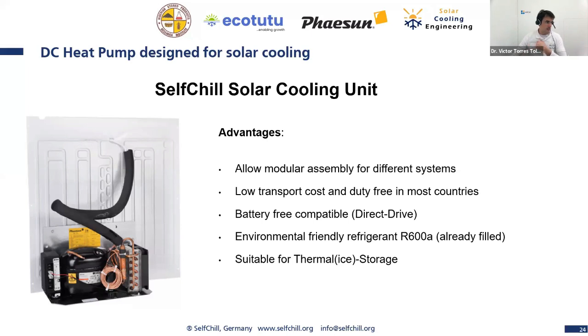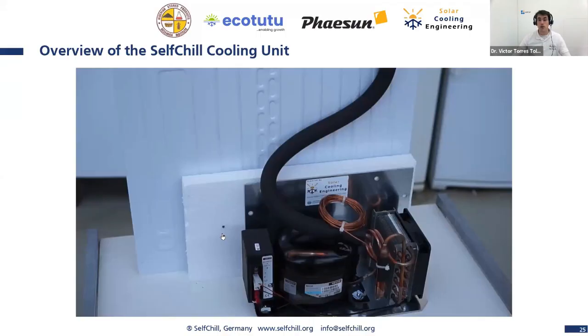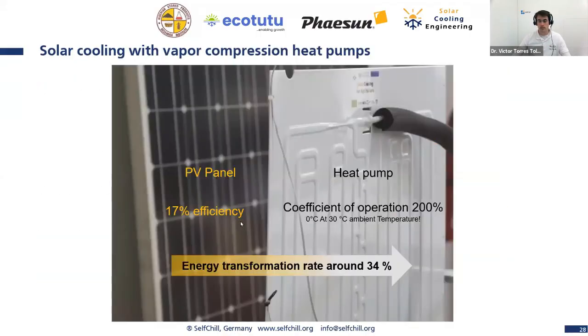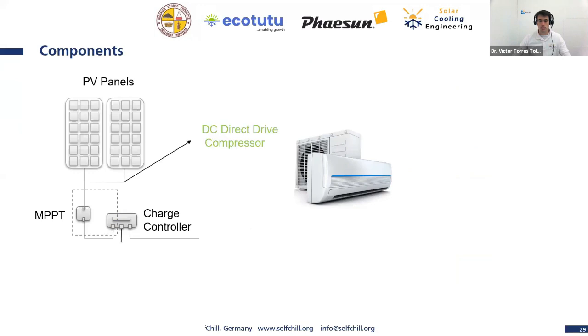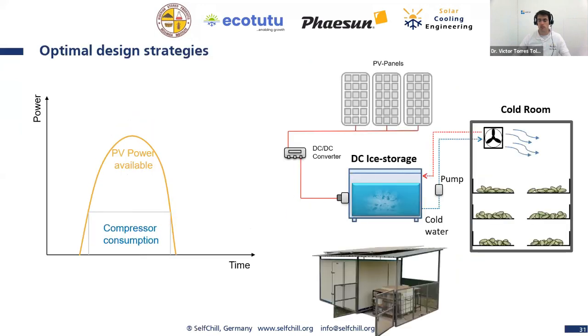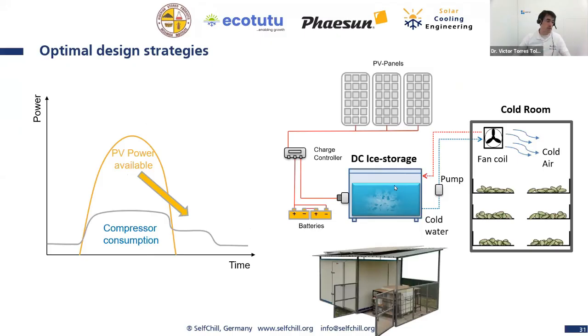I hope this has been understood. Please let us know if this solves your question, or if there are any questions. We prefer to solve them on the fly. So the refrigerant of the cooling units is inside the cooling units, inside the heat pumps, and the cooling medium is the water. Don't confuse it. We have a refrigerant, but we have also water that is then being pumped inside the cold room. Just normal water, nothing else.